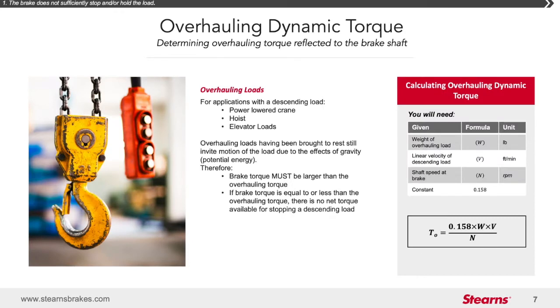Overhauling loads such as a hoist, lift, or elevator have two requirements: the braking torque required to stop the load and the torque required to hold the load at rest. The formula for calculating this is dynamic torque is equal to 0.158 times the weight of the load times the velocity of the descending load, represented in feet per minute, divided by the RPM of the motor.